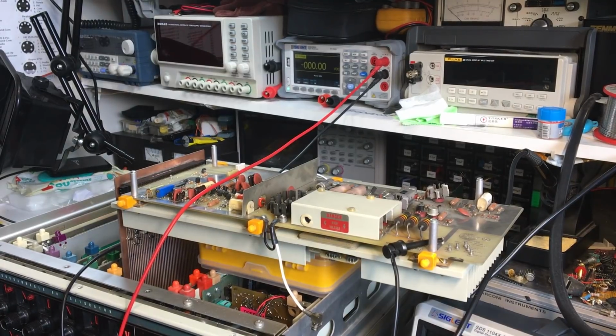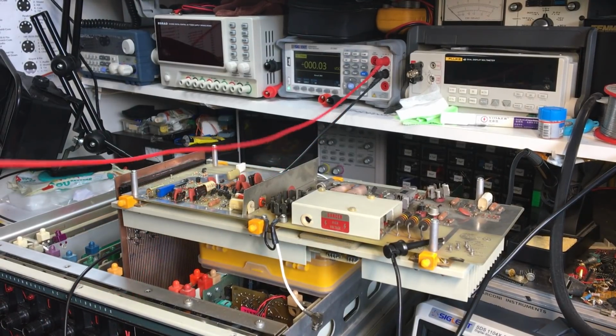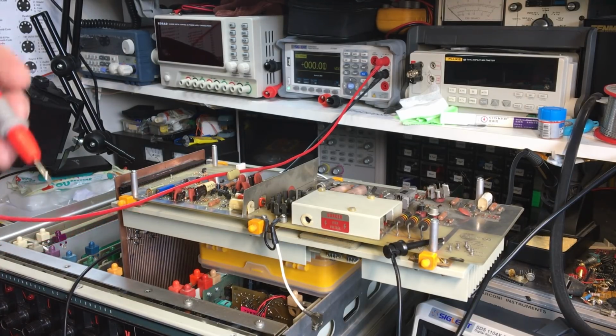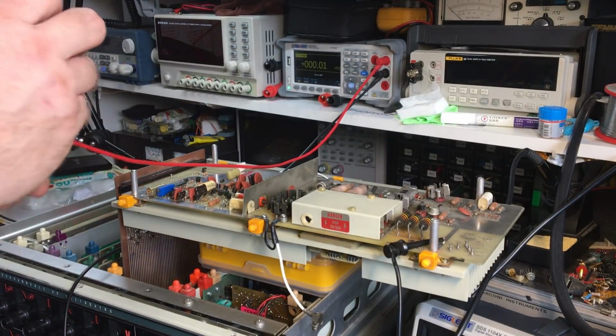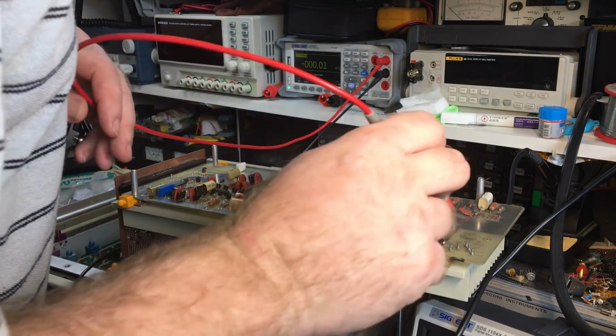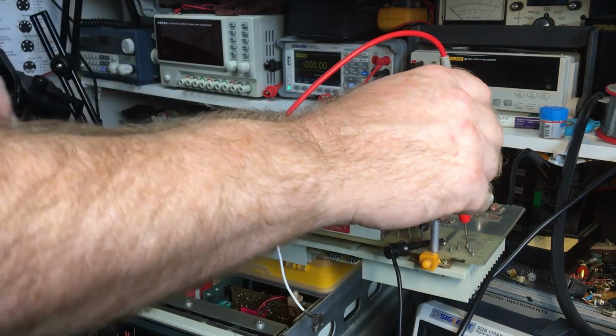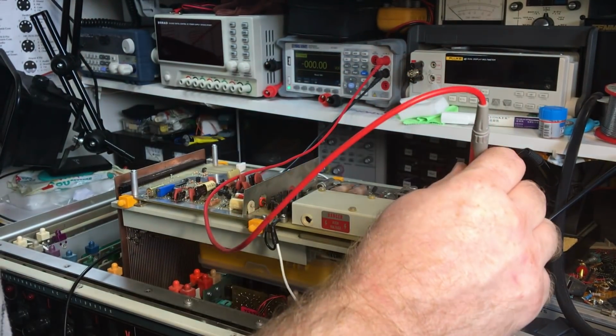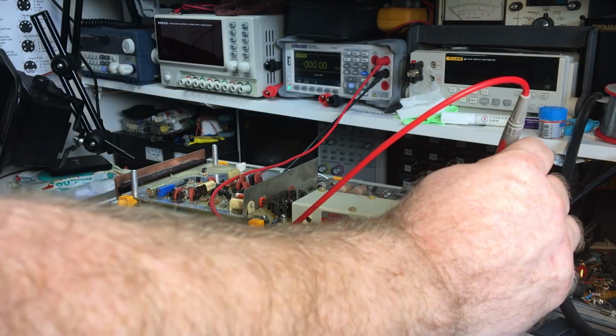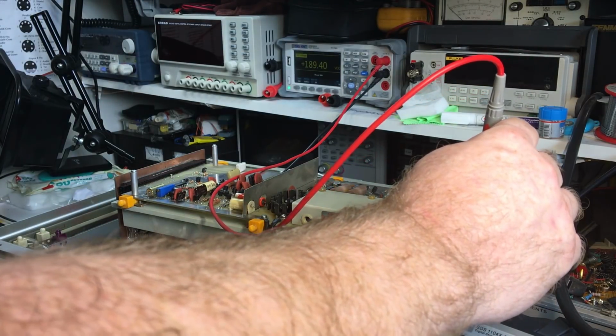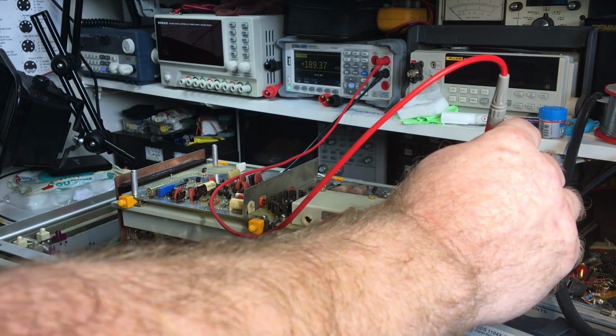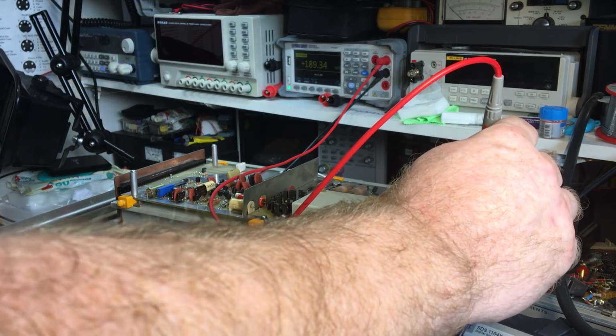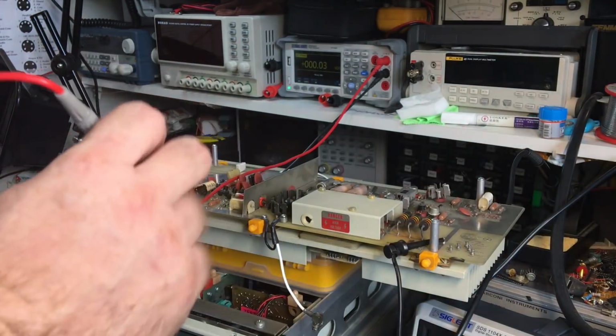Okay, the next step is step 37, and this is to check the plus 190 volt supply. It's got to be between plus 185 and plus 200, and this is at TP3. Where's TP3? TP3 right there. Okay, let's test that. Hope I'm not in the way of the meter. There you go, 189 volts. Looks fine. No issue there.